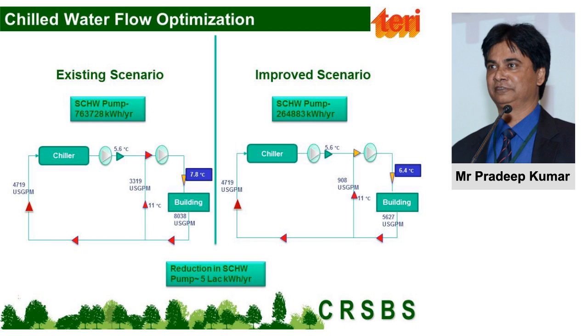365 days. So what we suggested, we manually operated the VFDs at a fixed frequency so that this bypass water quantity is reduced to 908 instead of 3319 USG. And the impact of that: now this much amount is going to be fixed with 5.6 of this mass flow rate. So the supplied chilled water temperature to the AHU coils dropped to 6.4, enough to dehumidify all the air and control the humidity.